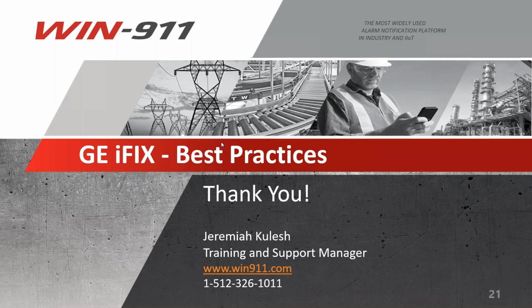So, really, what I would recommend is, if you must be notified when it's cleared, you're going to have to use the stop condition of when it's terminal instead of when it's acknowledged. And you might have to step up to the advanced strategies and tactics license to make that happen. Yeah, there's not a simple solution to that one for your needs in the Interactive.